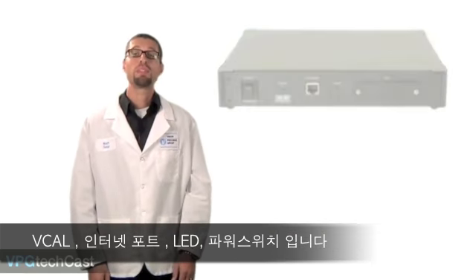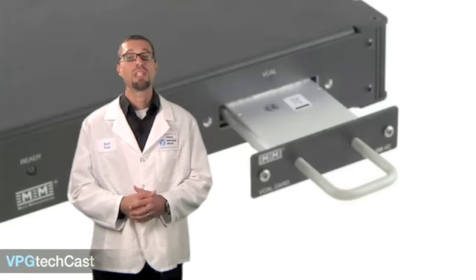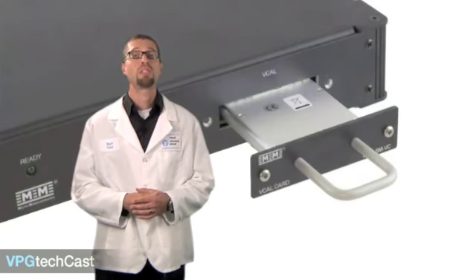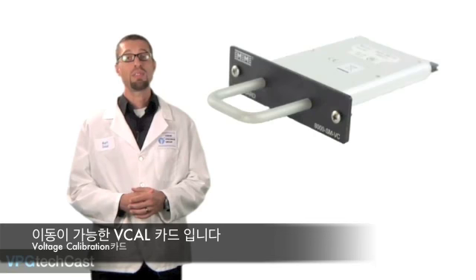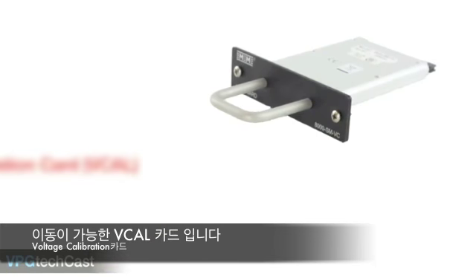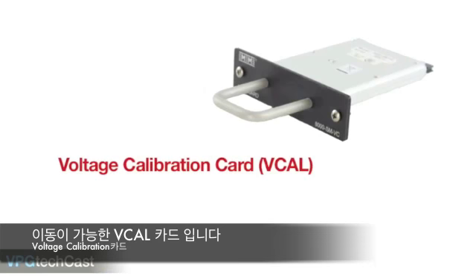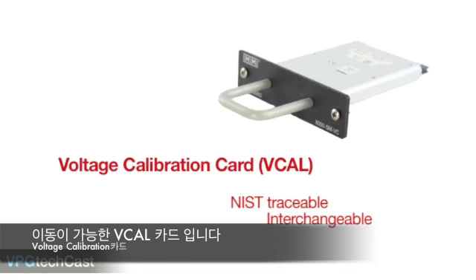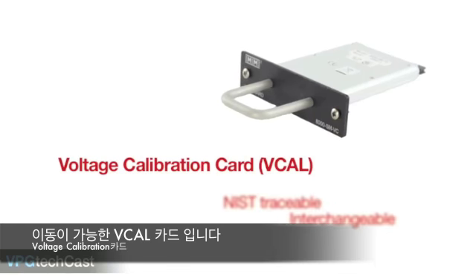Every 8000 can be self-calibrated and comes with an input slot designed to accept our removable voltage calibration card, or VCAL card. This optional accessory is an NIST traceable calibration device. It provides a high accuracy voltage source that is used to calibrate the gain and offset of each channel. The VCAL card can be interchangeable among different 8000s and is only required during the self-calibration process.